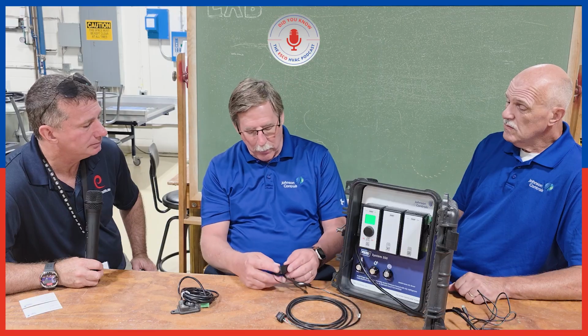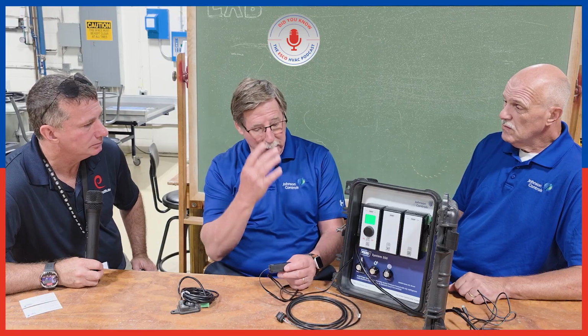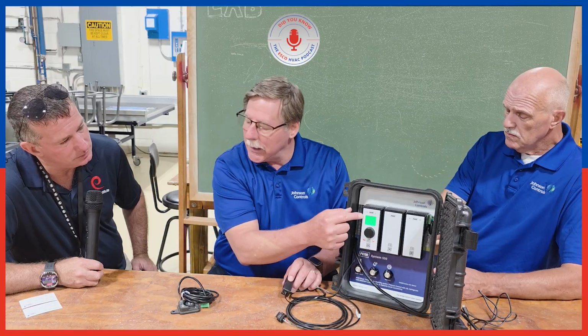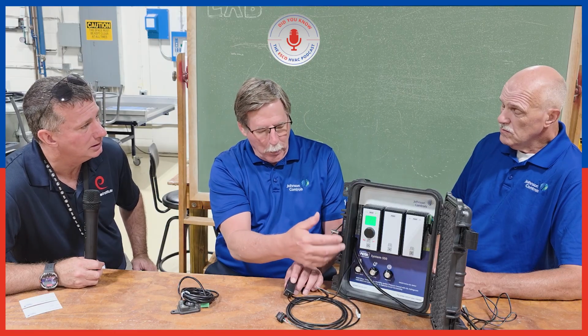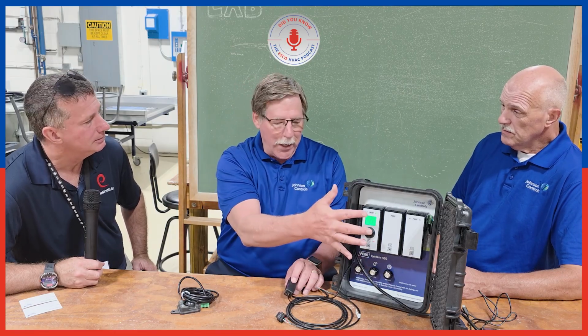Absolutely. I'm now going to assume that the leak is stopped, or at least the amount of refrigerant that has leaked out has dissipated. So I'm going to clear my leak, and now you can see that I've gone into a countdown. By the UL standard, I have to keep it in this kind of wait mode for 5 minutes, a transition soft lockout mode. The new firmware that we have will actually count this down. Right now, I just have to wait for this 5 minutes. Once it's done, I can confirm the alarm and it will go back into its normal mode.